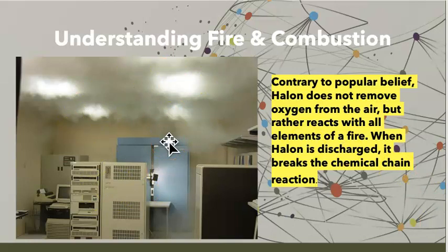These are just different pictures of a halon release. The CO2 is going to have a cooling effect and a choking effect, but the halon itself breaks the chain reaction. When we use these gases, we do no damage to all of this computer equipment that might be in a server room or whatever. This stuff is really expensive, the equipment, and halon is actually really expensive. We're not going to use it unless we're protecting these types of facilities.